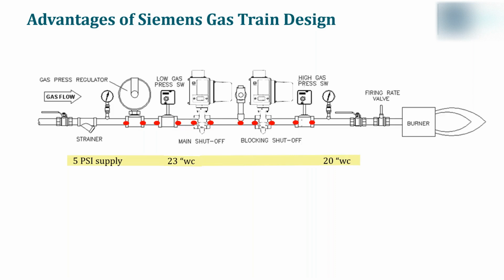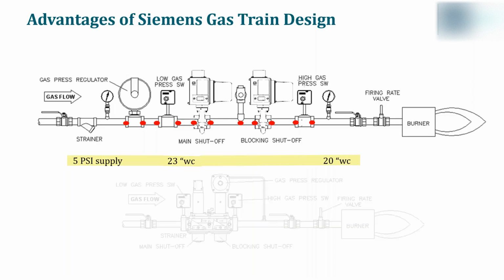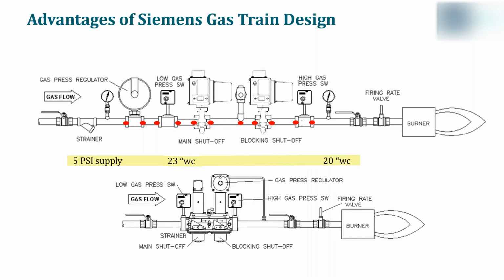Therefore, for this size boiler, gas train will probably be 3-inch based on these conditions. Now, let's take a look at the Siemens gas train design. First, you will notice there's only 2 connections, so the possibility of leakage is greatly reduced. Next, the regulator is the secondary safety shutoff valve, and the pressure drop occurs at this valve. Finally, the downstream sensing line before the firing rate valve maintains a pressure of 20 inches water column.